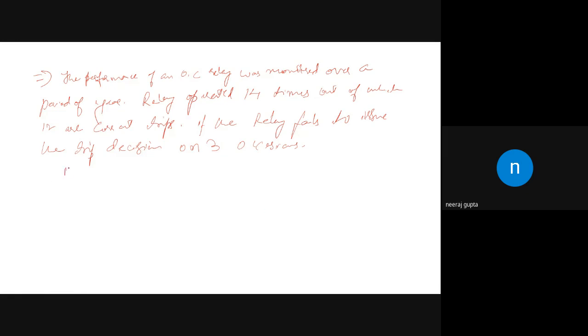As you know, dependability is given by the number of correct trips divided by the number of desired trips, into 100. The number of correct trips is 12 in this case. What are the desired trips? Desired are 12 plus 3, where no decision occurs, so we have 15, into 100. So it is 80%.